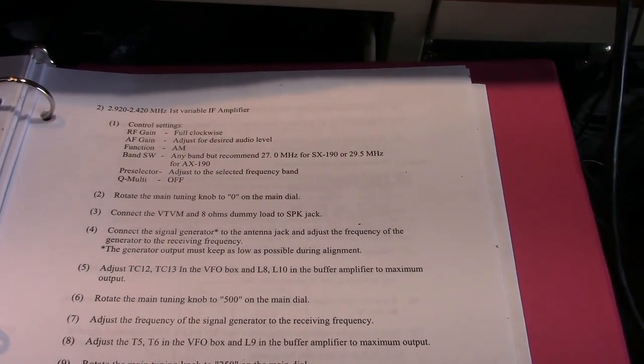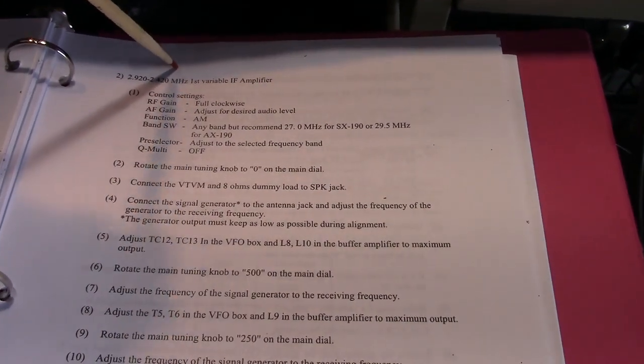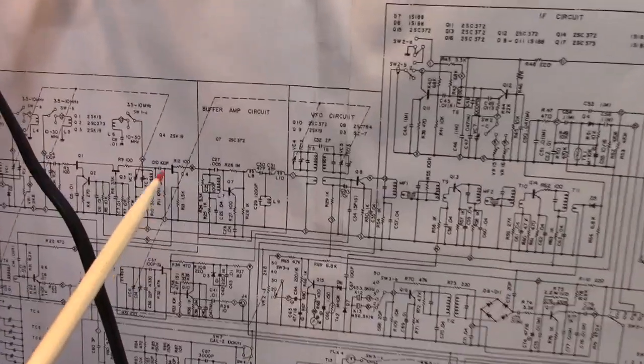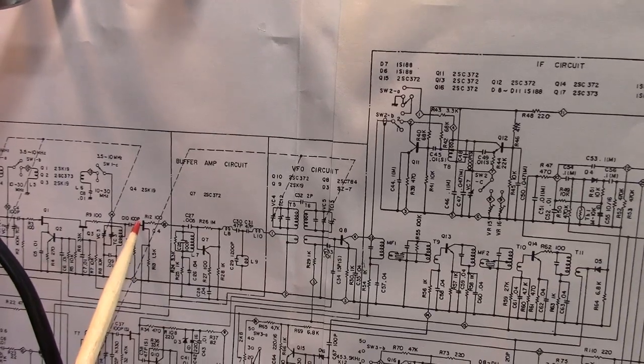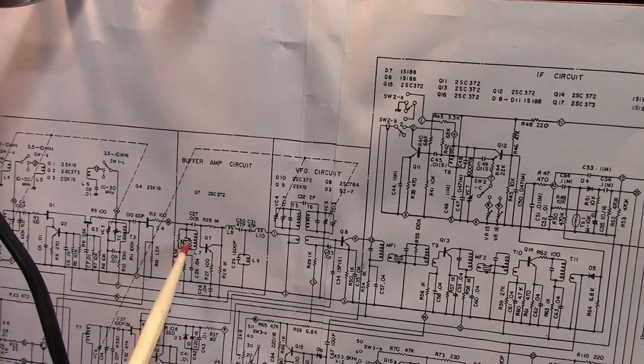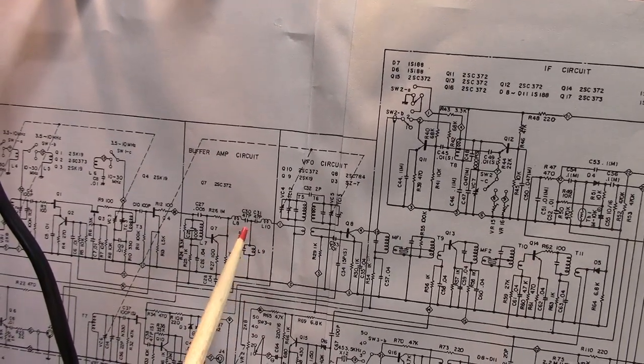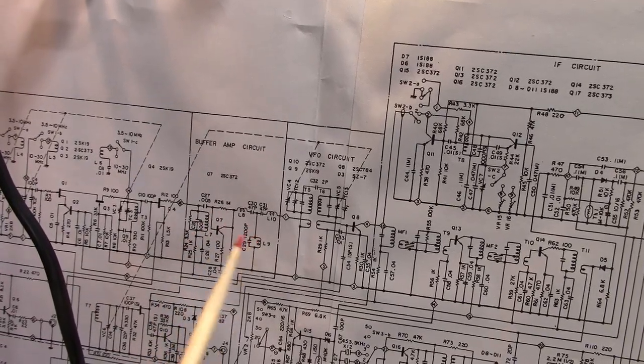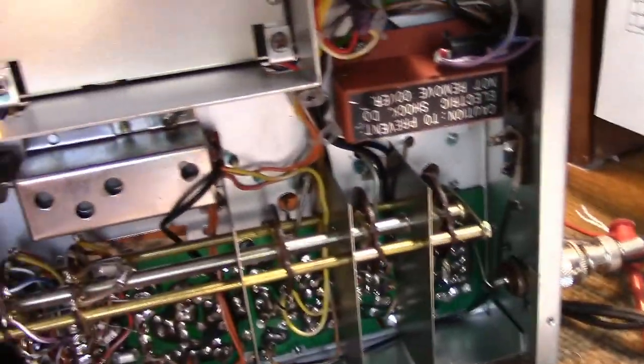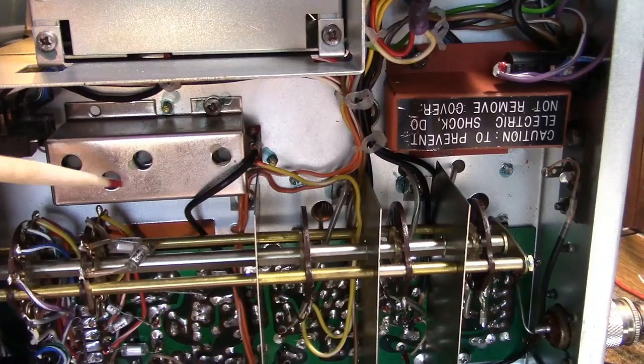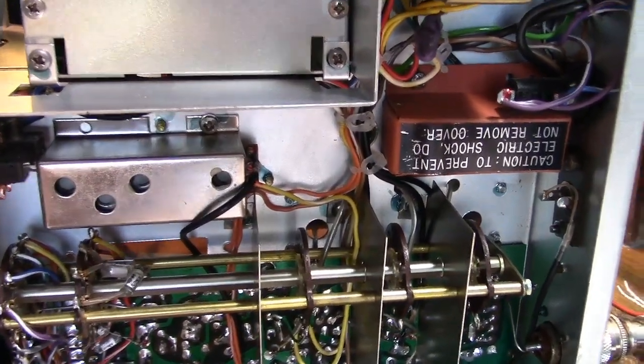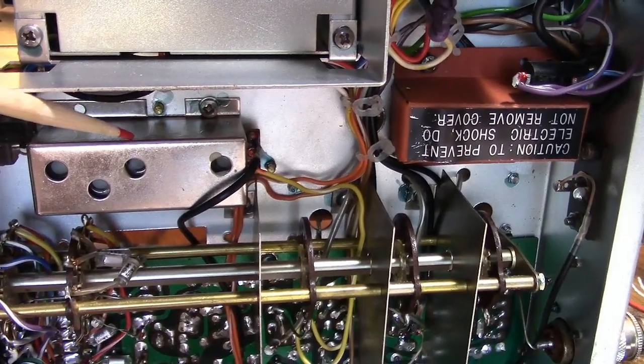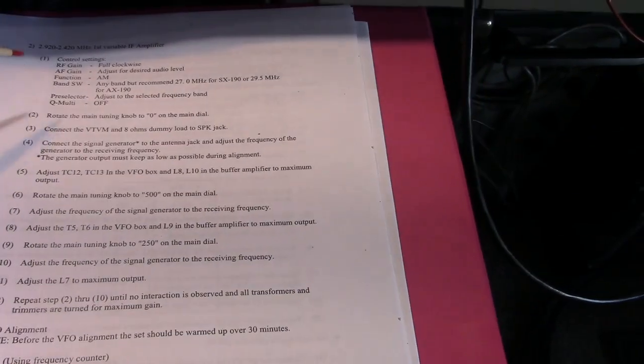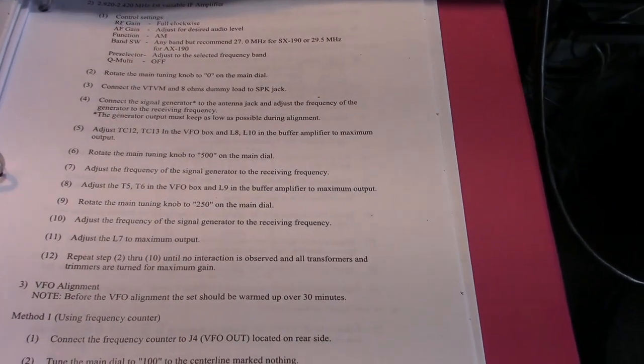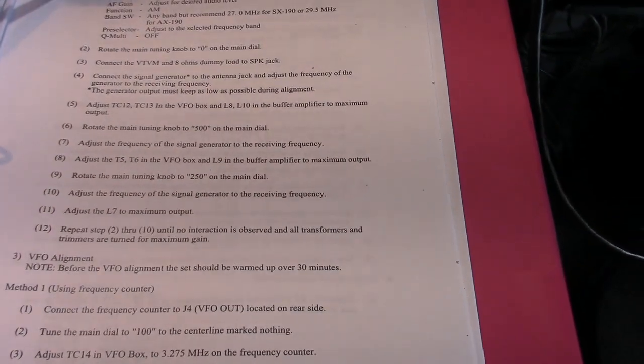The next step calls for adjusting the first IF variable amplifier. This is in the buffer amplifier, which is this stage here. Here's Q4, your first mixer, and here's your buffer amp here. And they call for adjusting L9, 10, 8, and 7. 7, 8, 9, and 10. Those controls are located in this shielded box here, and these have sealing wax on them, and I really have no reason to suspect they're out of alignment, so I'm not going to dig the wax out and make an attempt to adjust these. Like I said, the thing seems to be working okay up to there, so if you have one of these and it's out of adjustment, you can follow the instructions on page 5 of the alignment procedures. That would be here.